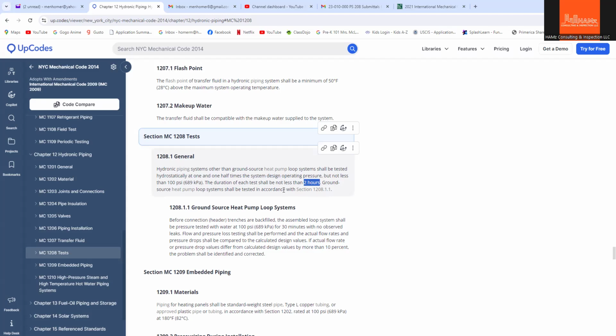Sometimes I witness some system modification. They're just going to install a new piping system that will be attached to the existing system. And sometimes the existing system is operating at only 5 psi or 10 psi. So the contractor will say it's 1.5 times the operating pressure, so for 10 psi we should only test it at 15 psi. So it depends on the situation. I always tell them if it's a new pipe, we only need to test the new pipe, and we should isolate the existing piping system so that we don't blow it up or burst some connection on the system, because it's not part of the job. So if it's a new piping system, regardless of the operating pressure, it should not be less than 100 psi.